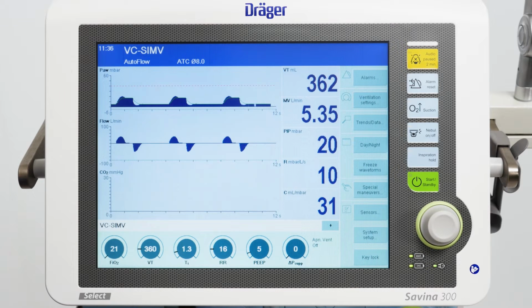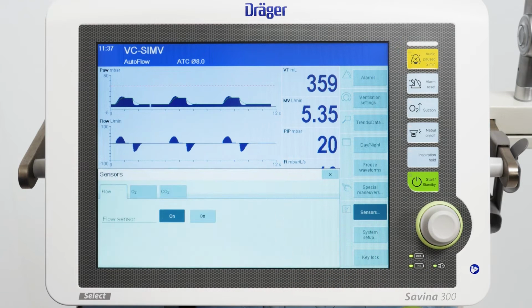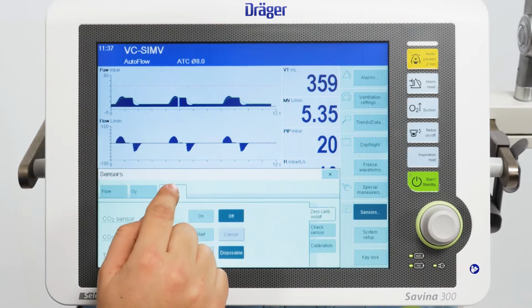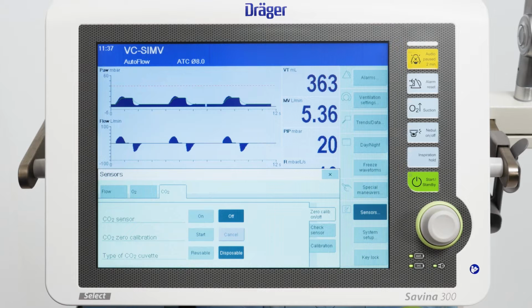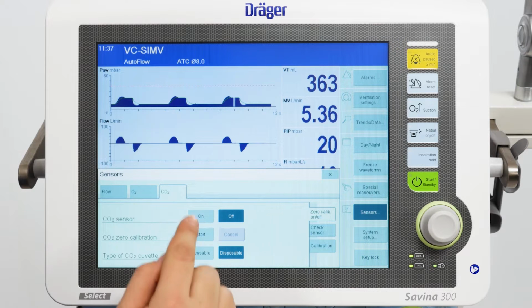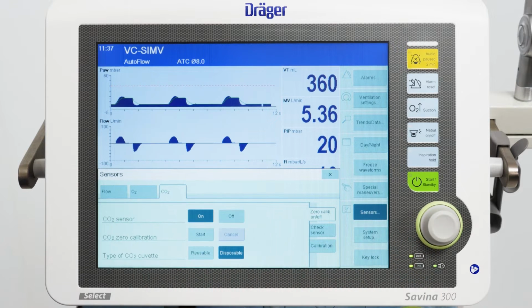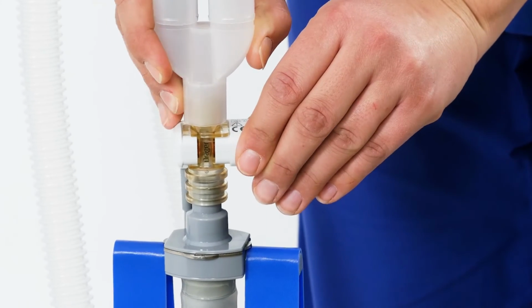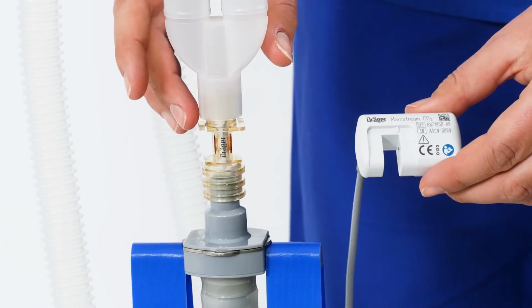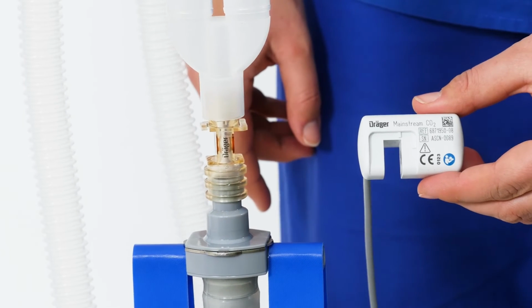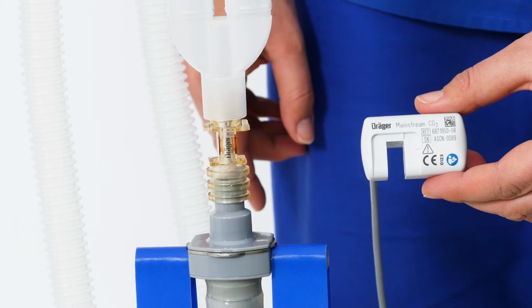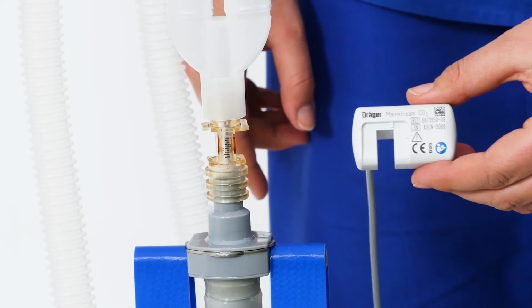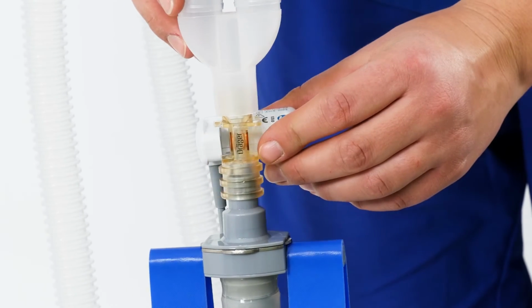Select the cuvette type and display the CO2 measured values as a curve in the curve field. Touch the Sensors button in the main menu bar and then touch the CO2 tab. Select the cuvette type and touch the Start button and confirm with the rotary knob. When requested by Savina 300 Select, remove the CO2 sensor from the cuvette and hold in ambient air. Do not breathe on or into the cuvette.